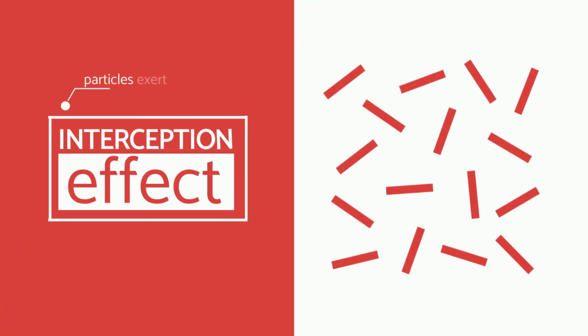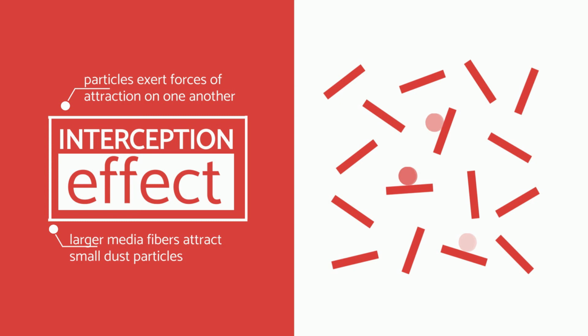Third is the interception effect. We learned earlier that particles exert forces of attraction on one another, and that's the principle at play here. Larger media fibers attract small dust particles. Once the small dust particles have been intercepted, they get stuck between the media fibers.